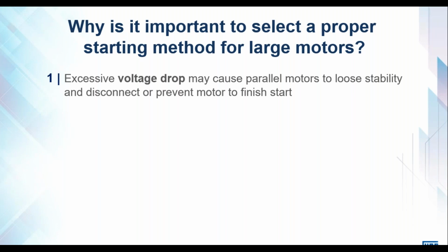Okay, so these are pretty common knowledge to most engineers. Why is it important to select a proper starting method for large motors? Well, voltage drop. When you have a voltage drop at the terminal of a motor, the torque decreases to the square of that voltage drop. So this is something to consider.